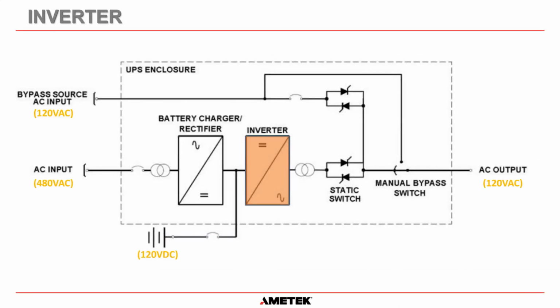The next block is the inverter. Okay, this converts the DC that the charger just made back into AC. So you can see here on the left-hand side, we've got our positive over here, and we have our negative over here. So this is our DC. And then instead of having SCRs, we now have 4, because this is a small system, we have 4 IGBTs, which are insulated gate bipolar transistors. And this is what changes the DC back into AC.